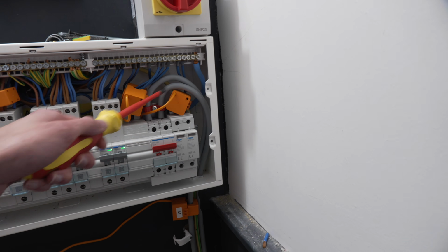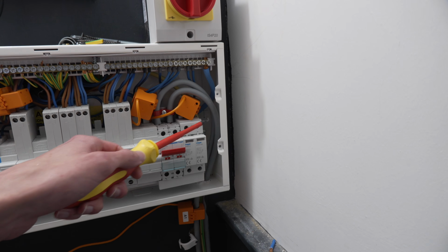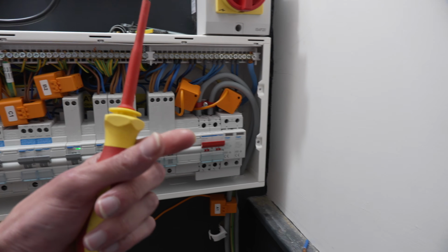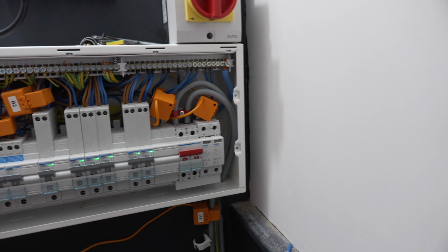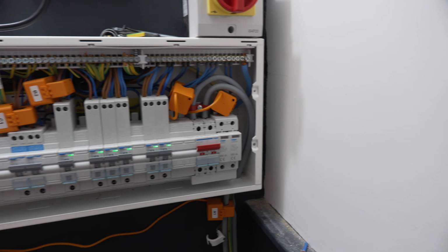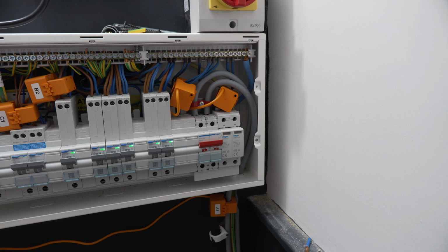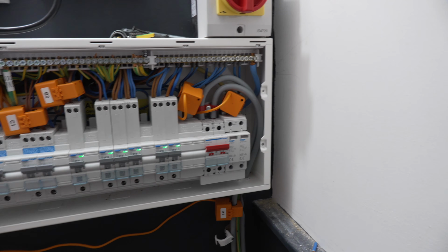There's not really any flexibility to bend them, so trying to get a CT in this area would have just been a bit awkward. The other thing you need to watch is that the core in these CTs is a ferrite core, and it's very brittle, so you do not want to force them, clamping them around something where you're squeezing it shut, because the risk is that you'll crack the core and destroy the CT.